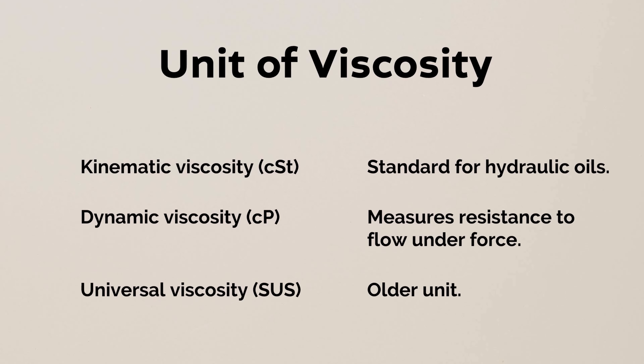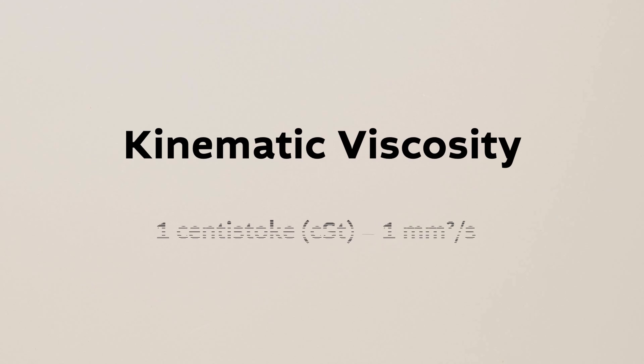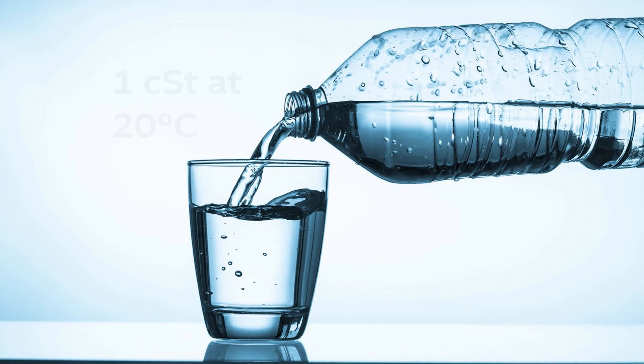Viscosity is measured in three different ways: kinematic viscosity, dynamic viscosity, and universal viscosity. For hydraulic oil we use kinematic viscosity in centistokes. One centistoke equals 1 mm² per second in metric units. For reference, water has a viscosity of 1 centistoke at 20 degrees centigrade.